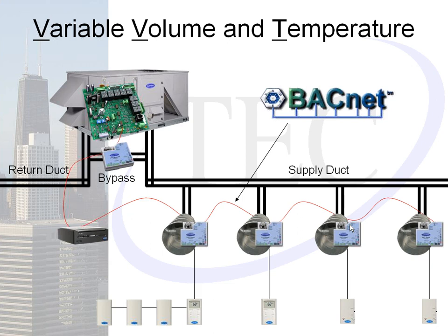Here's roughly what the system looks like: a rooftop unit, supply ductwork, a bypass duct, a controller in the rooftop unit, a controller at the bypass damper, and individual zone dampers in each zone — each with its own temperature sensor — all wired to a communication bus. One of those zone dampers is established as the linkage master, which dictates which operating mode the rooftop is in. An optional iVu web appliance can also be added to give customers more control over their facility.